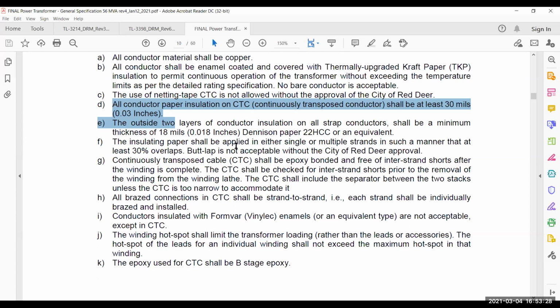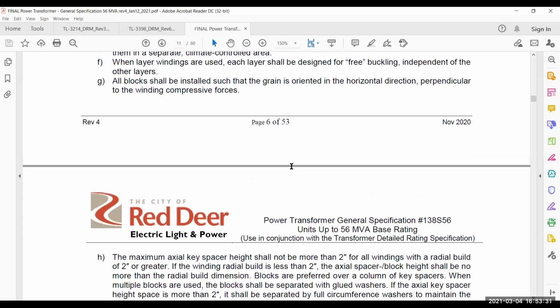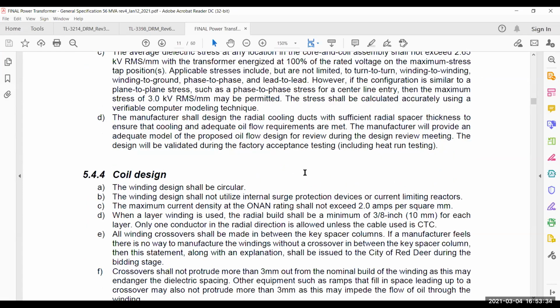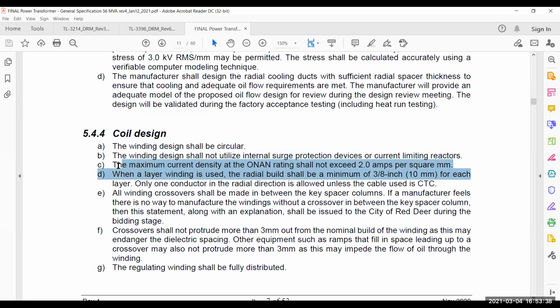Not only that, another thing that we put in the specification that can force the manufacturer to be more conservative in the design, number C, is that the maximum current density at the ONAN rating shall not exceed 2 amps per square millimeter. What does it mean? It is forcing the manufacturer to be more conservative in thermal design so that the transformer is not designed close to the temperature which can cost the life of the transformer. So in the design review stage, we will cross-check and force the manufacturer to implement those things.